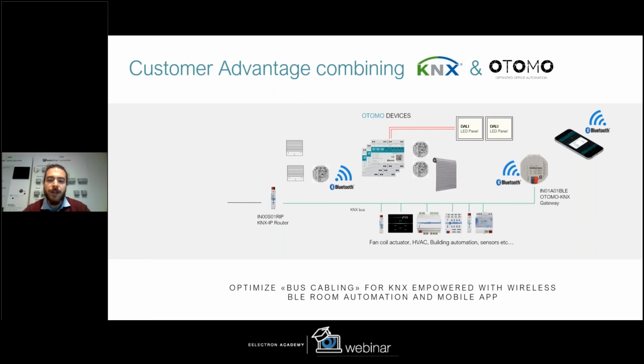Think about a system where KNX is already installed, and the end user asks you to add light management or control to a part of the building where you can't rewire the KNX system. But you already have phase and neutral in the back box or derivation box for the lighting system. Here, very easily, we can put the Otomo actuator, and thanks to the gateway, we can control and manage this light without any problem.